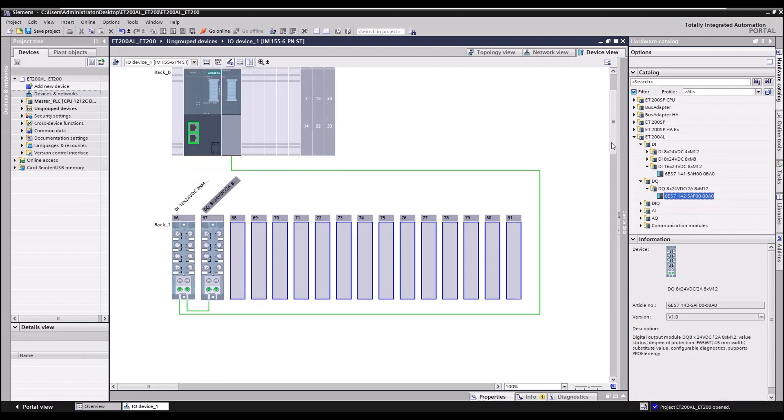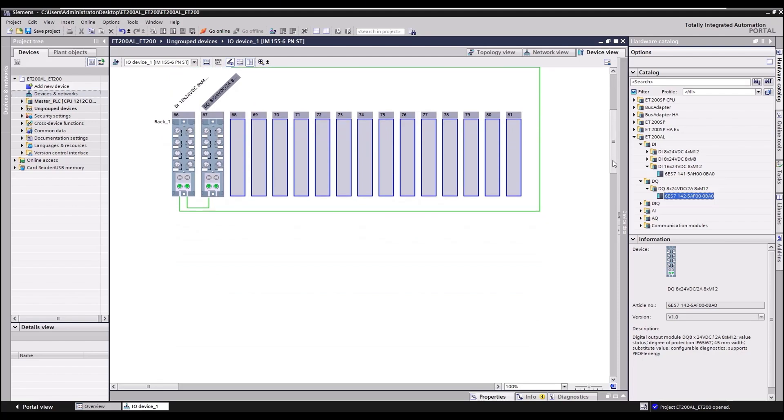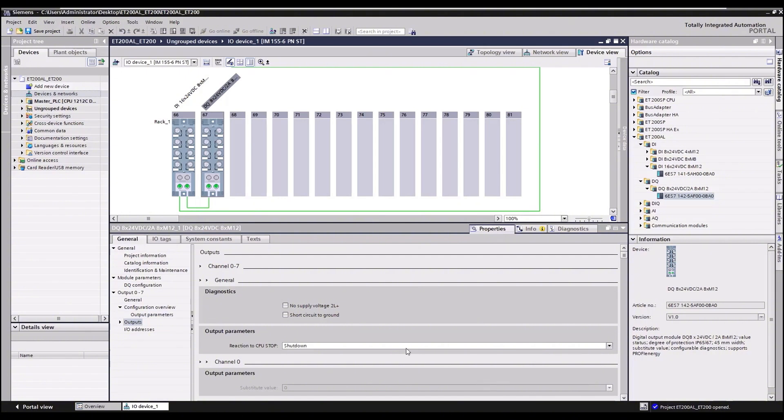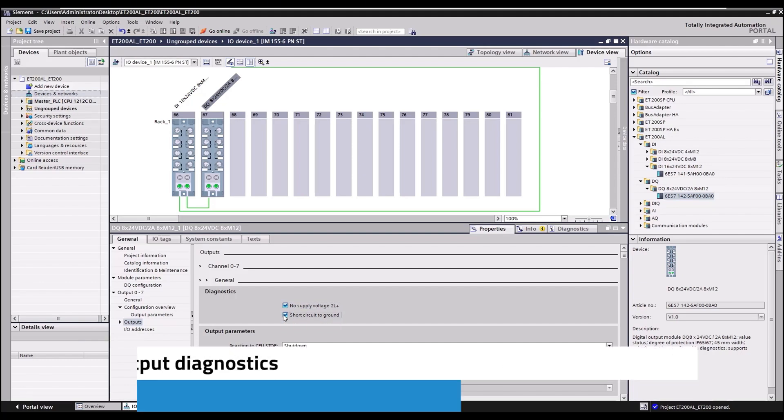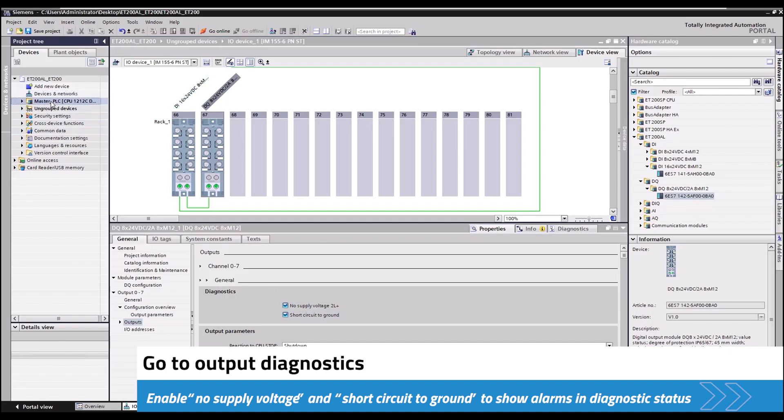Expand the properties section of the lower part of the screen. Since the 8-point DQ was the last item added, the properties shown are from that item. Go to output diagnostics, enable no supply voltage, short circuit to ground. These alarms will automatically show up in the diagnostic status.